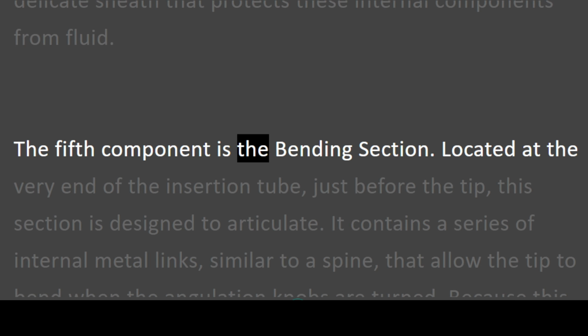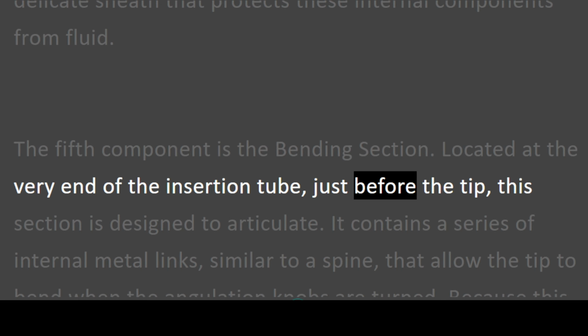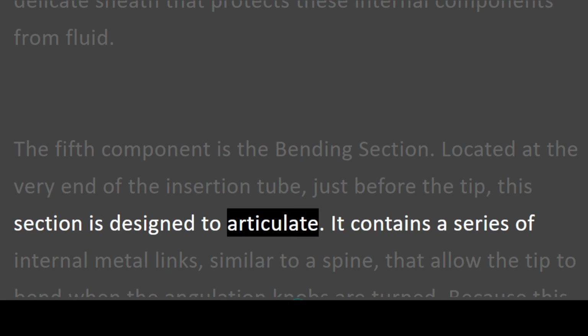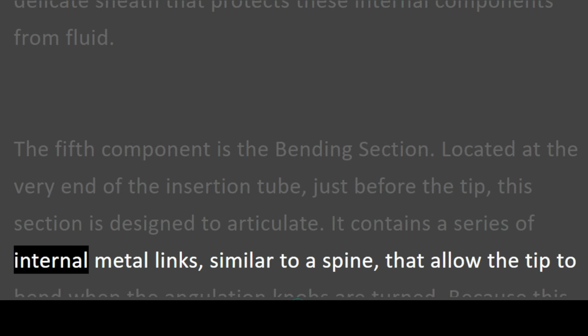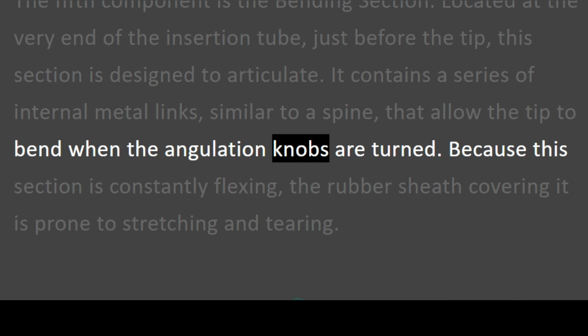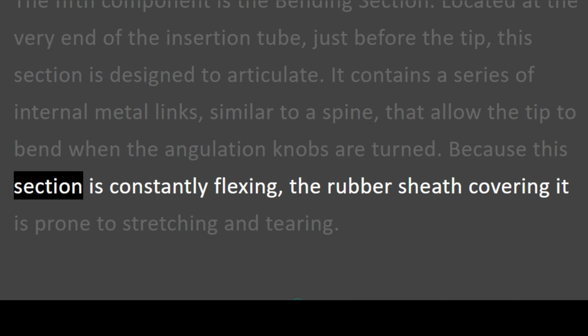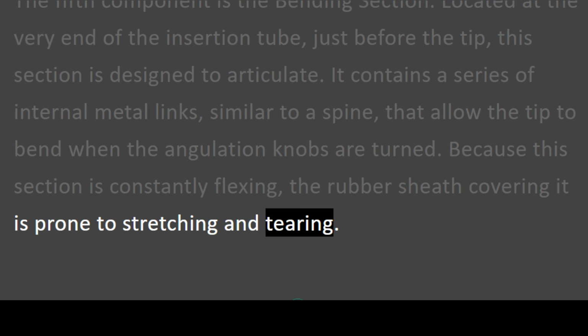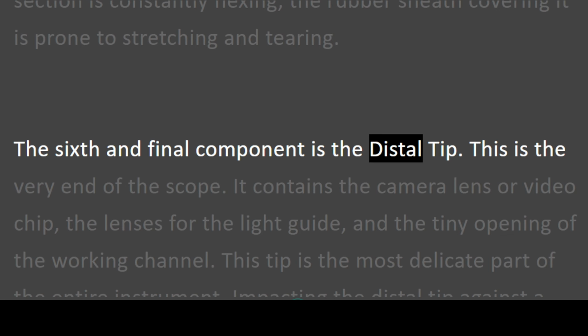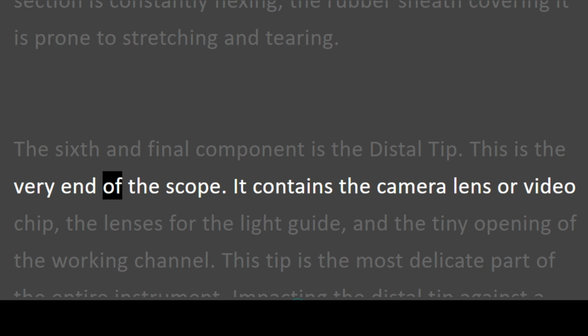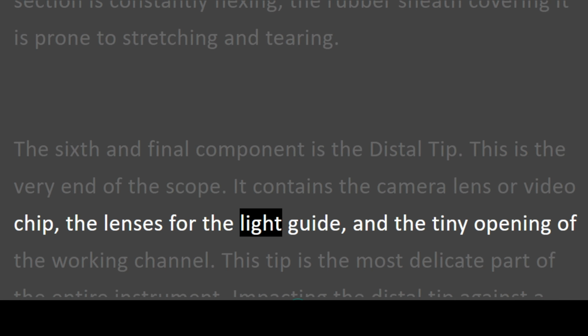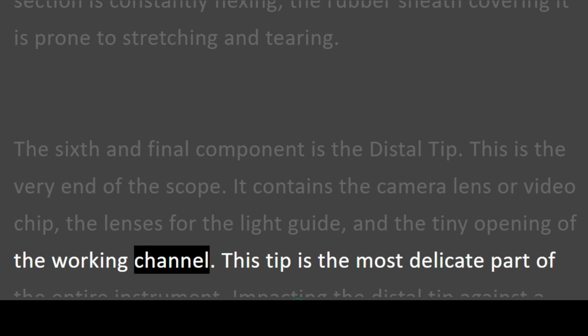The fifth component is the bending section. Located at the very end of the insertion tube, just before the tip, this section is designed to articulate. It contains a series of internal metal links, similar to a spine, that allow the tip to bend when the angulation knobs are turned. Because this section is constantly flexing, the rubber sheath covering it is prone to stretching and tearing. The sixth and final component is the distal tip. This is the very end of the scope. It contains the camera lens or video chip, the lenses for the light guide, and the tiny opening of the working channel.